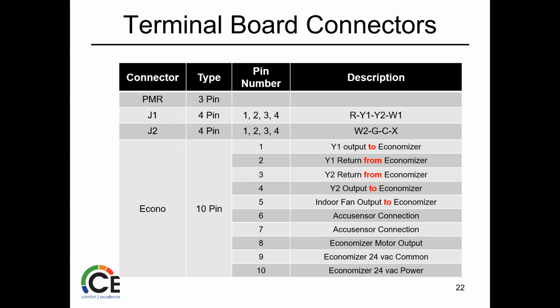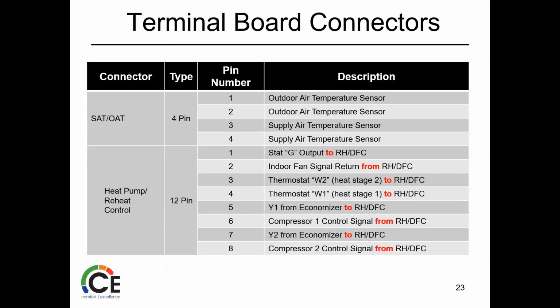There's an output to it, which is from the thermostat, then it returns from the economizer, and then it starts to hit the contactor or the pressure switches or whatever's going on there. So the biggest thing to remember there is terminals 1 through 4, that they are used in cooling operation. So that's hint, hint, test question: what are those 4 used for? All right. And why is it important for you to know that? SAT, OAT, pretty simple.